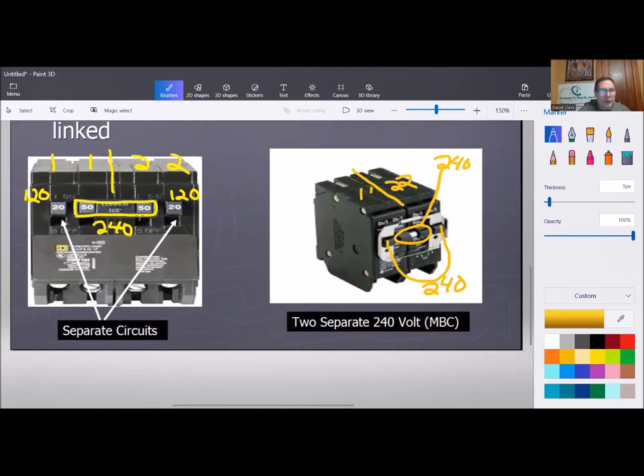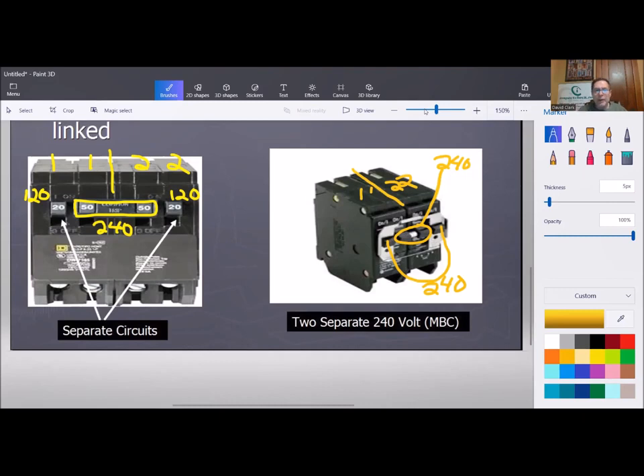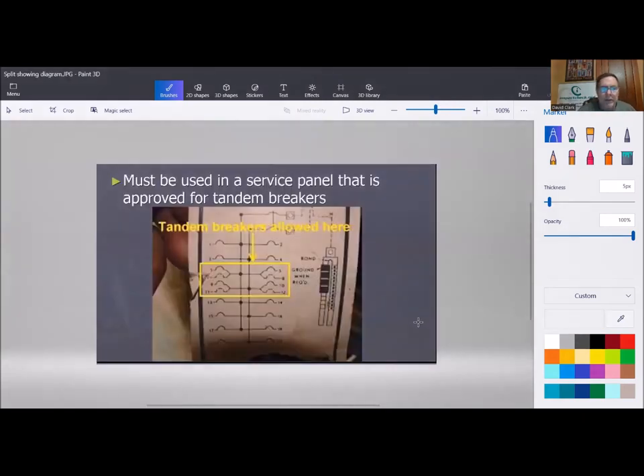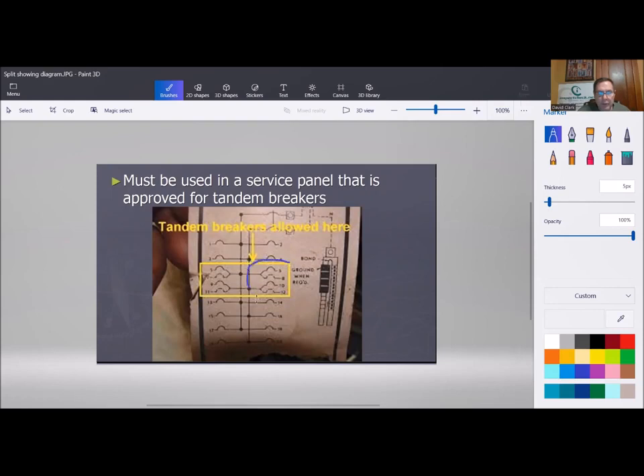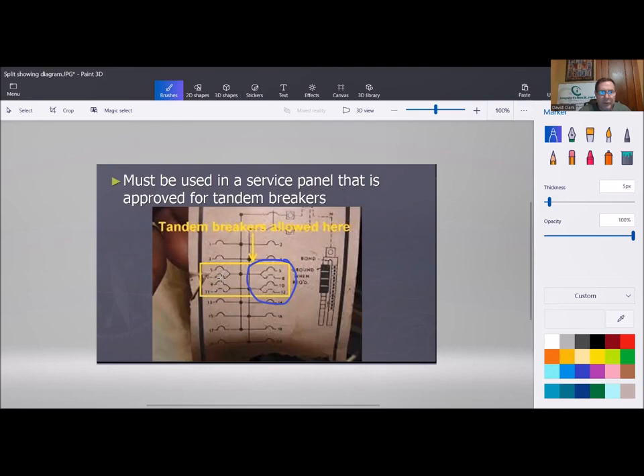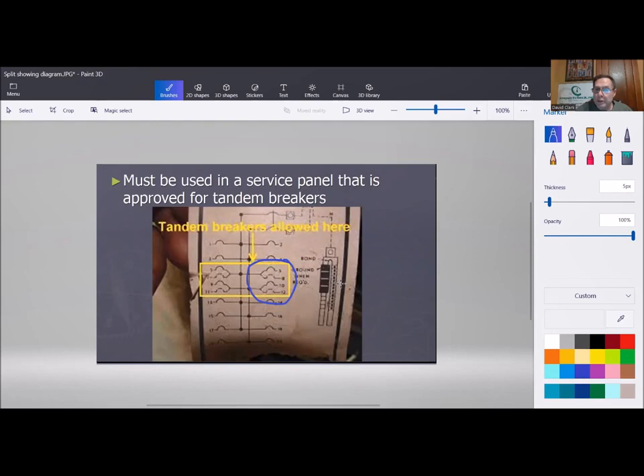So again, if this were a multi-branch circuit, this would be 15 or 20, and they're internally, and we can use that. We'll talk more about multi-branch circuits. I'm going to do another video on that. I get a lot of questions. So where can we use these? We said before that maybe that service panel is obsolete. So let's take a look at how we would know that. And how we would know that is because we would look at the legend inside the service panel, and it's going to tell us. So it says tandem breakers here. So if we look here, there's one line, one line, one breaker, one breaker, one breaker, and then here we're allowed tandems. So this would be the place right here where we could put a quad breaker. That would be the place or tandem breakers. But in this case, that breaker we just saw, that's where it would be. So if this was the schematic for that panel, then we could use that. So hopefully that helped you out. And when you see that quad breaker, you understand how it works.